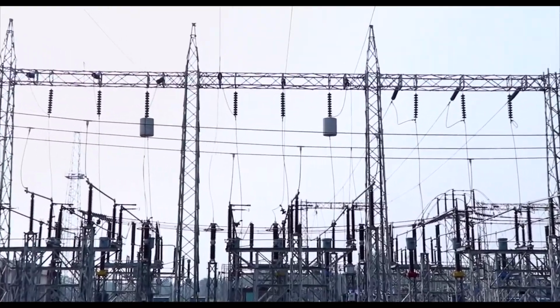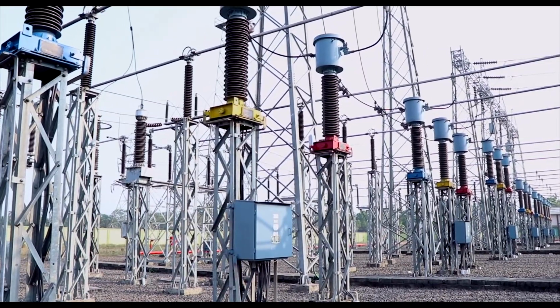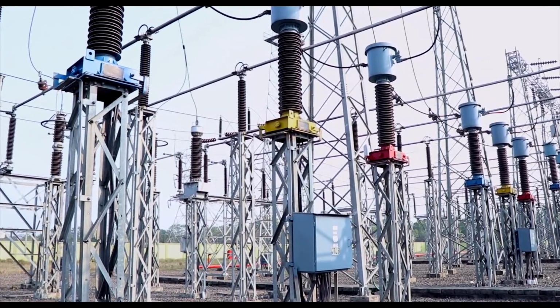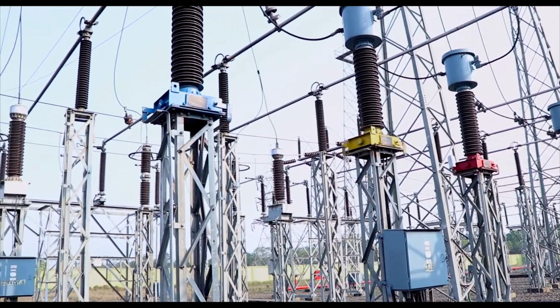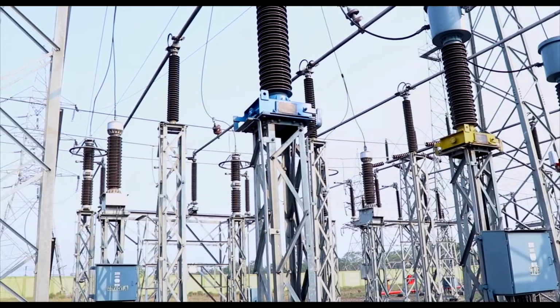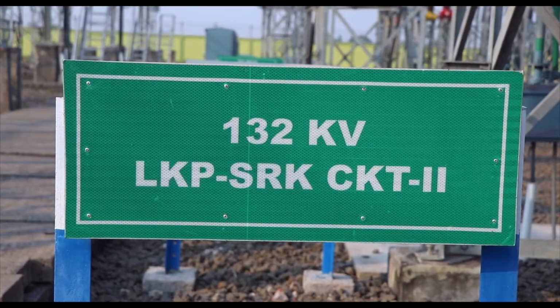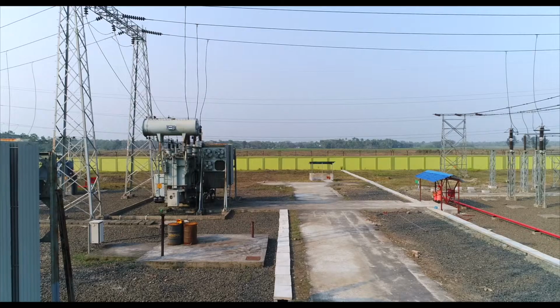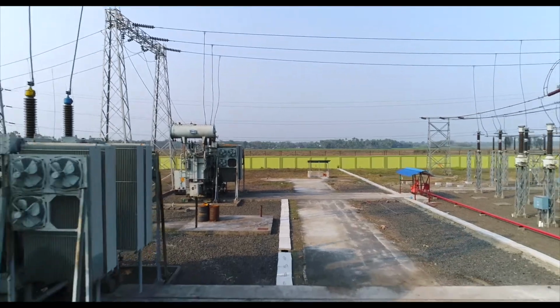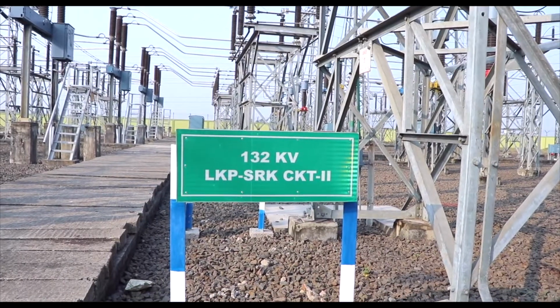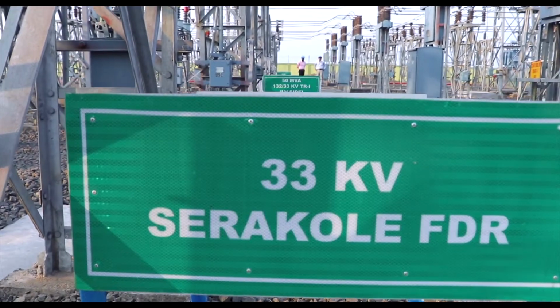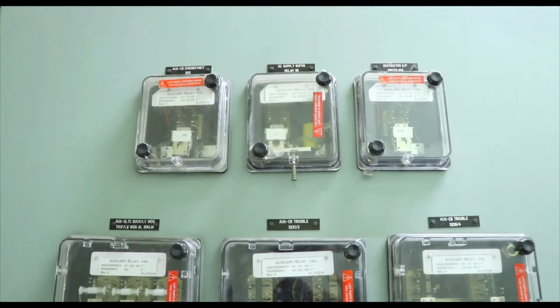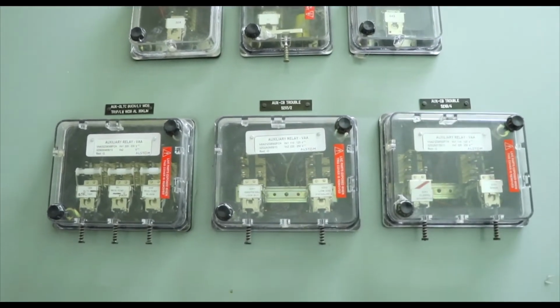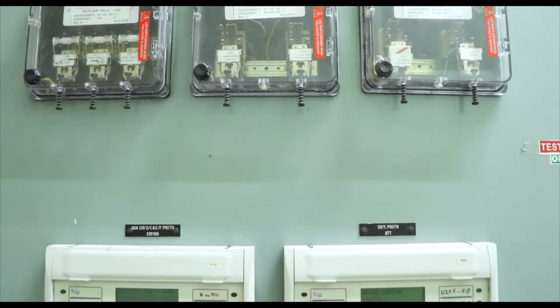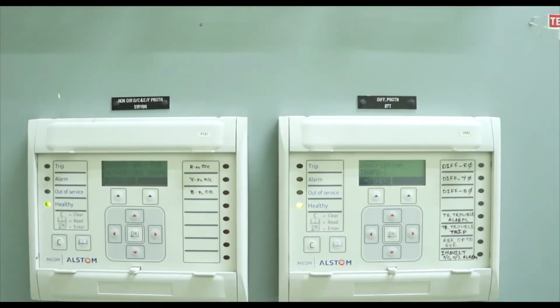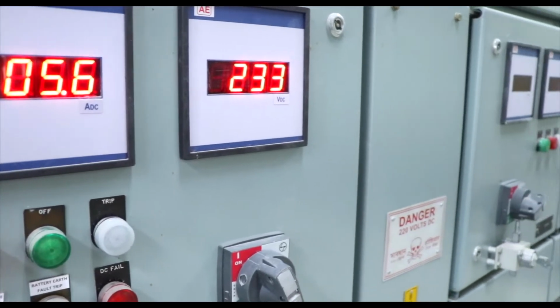For reliable transmission, there is one main bus and one transfer bus on both the 132 kV side and 33 kV side. Our 132 kV and 33 kV control and relay panels are equipped with multifunctional MiCOM numeric relays with disturbance recorder and static relays, digitalized metering. Also, we have a data recording system through offline SCADA via RTU panel.